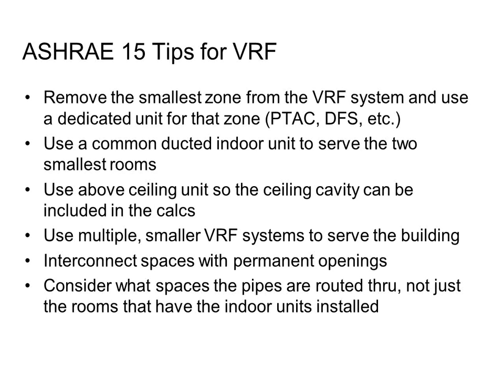Because every time we braze those pipes together, there's going to be a little bit of a bump there, right? So a little bit more friction, and some of those distances that they can go are friction dependent. So usually you look at the rules for the VRF manufacturers, and they'll be directing you to use ACR. That doesn't mean they'll prohibit you from using hard pipe. It's not ideal to use 20-foot sticks of pipe and get the same amount of length out of it. So for a lot of systems, it won't matter. I know in the Chicago area, the union guys like to use hard pipe and not use the pre-manufactured line sets. You can use both. The rules may change depending on your manufacturer.